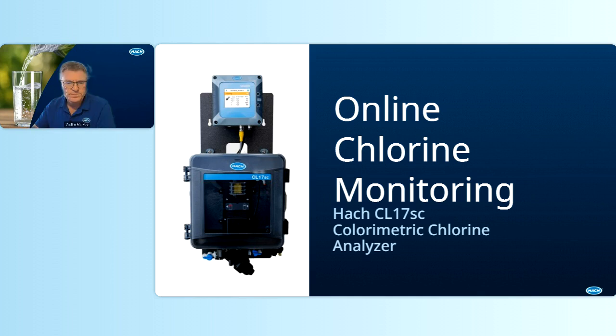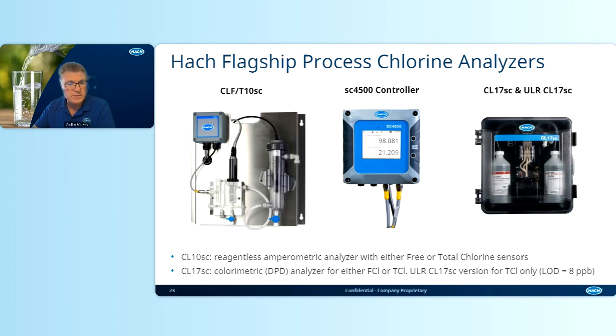Hello, everybody. Let's dive deeper into Hach instrumentation and particularly the colorimetric chlorine analyzer. And before we go there, this slide depicts the Hach flagship process chlorine analyzers. You see on the left-hand side, the amperometric analyzer, which reflects all the benefits Terry just highlighted in the previous section. It's reagentless, it responds fast to chlorine concentration changes, and it measures free or total chlorine with different sensors. On the right-hand side, there is a colorimetric analyzer, which provides accuracy all the time. It doesn't need calibration. So you can always have a choice between the fast response of amperometric and uncompromised accuracy of colorimetric.